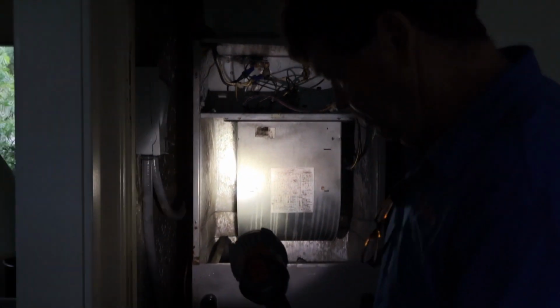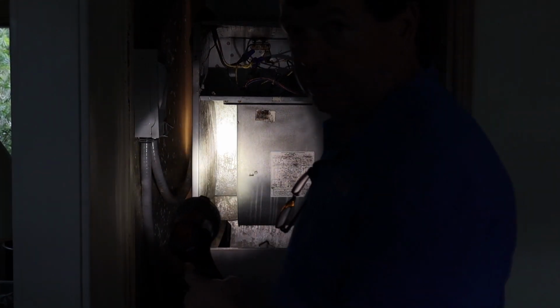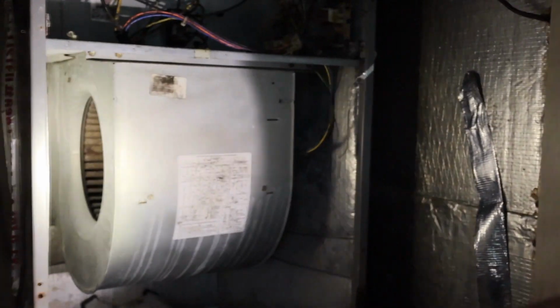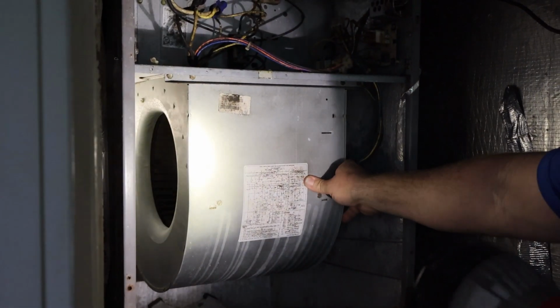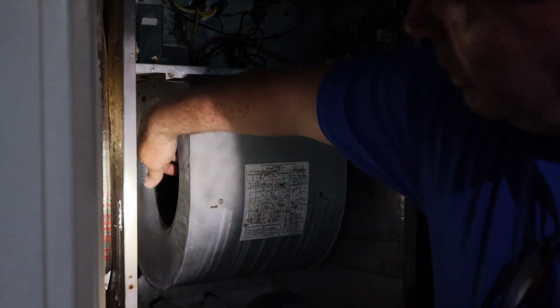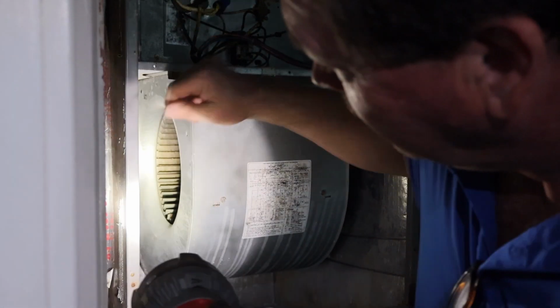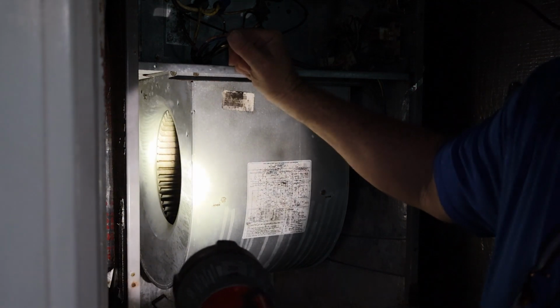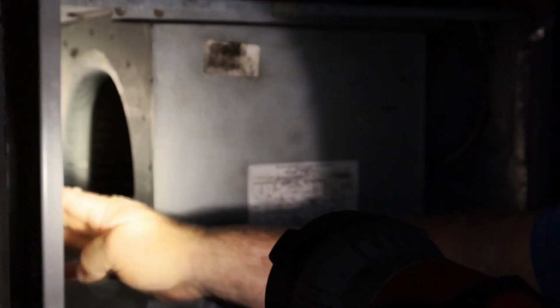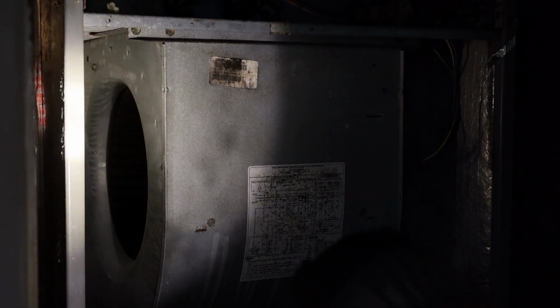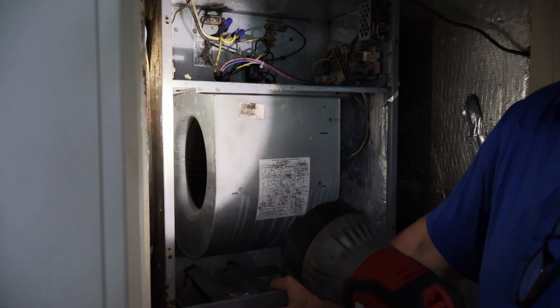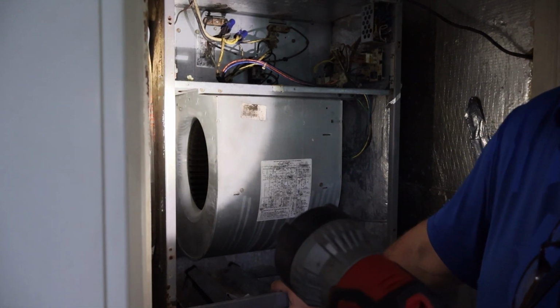Now, one of the areas that we could be a little more concerned about is the blower wheel. I don't know that you can see the blower wheel, but you may can move your camera over towards that opening, possibly. Yes, I see it now. What we're looking for is these louvers right here, if they've got a bunch of buildup in them. And if you look at it, very, very moderate, nothing to be concerned about. I don't think it warrants cleaning. Now, you know, we could always do maintenance plus, basic plus, excuse me.